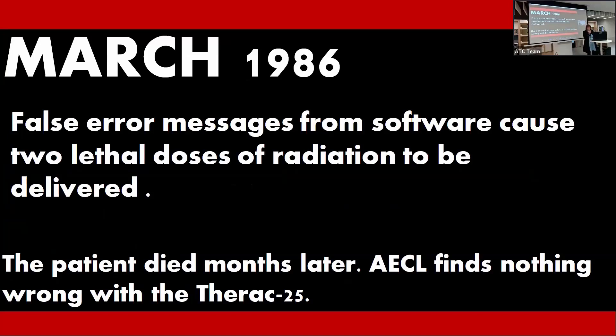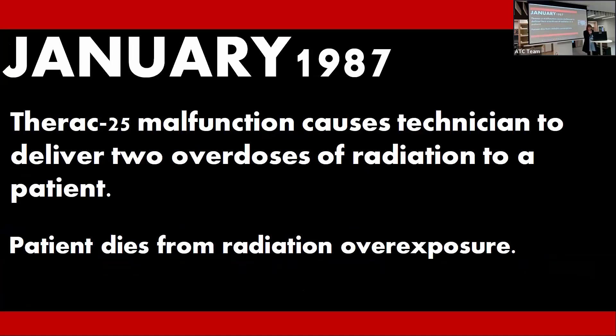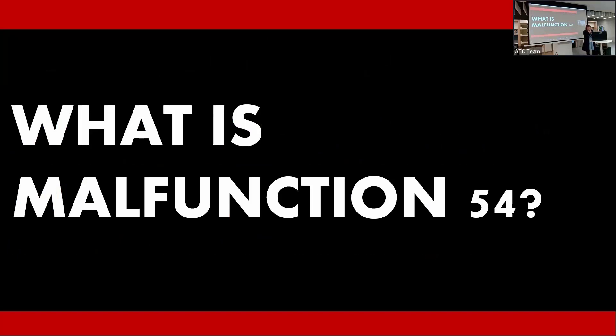In March 1986, false error messages from the software caused two lethal doses of radiation to be delivered to a patient. The patient died months later. AECL investigated but found nothing wrong with the Therac-25, still maintaining that an overdose was impossible. In April 1986, more false error messages, and another patient died from overexposure. The Therac-25 was briefly taken out of commission and looked into by the FDA, who requested some small hardware updates. Right after that, it was reinstated. In January 1987, a Therac-25 malfunction caused a technician to deliver two overdoses of radiation to a patient, who died from overexposure. All cases of the deaths included an error message called malfunction 54 appearing on the screen. Malfunction 54 was not described in the manual given to technicians — it was a cryptic message that would show up, and they could easily bypass it by pressing P on the keyboard to proceed.